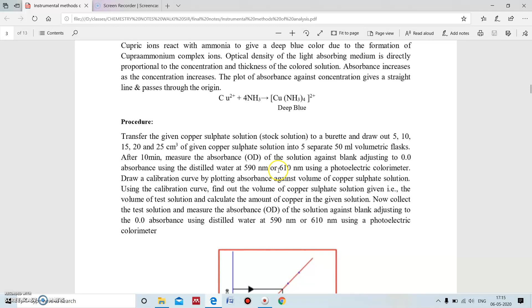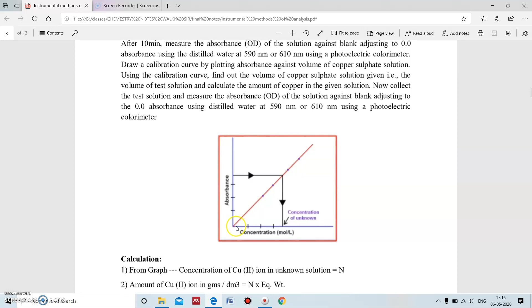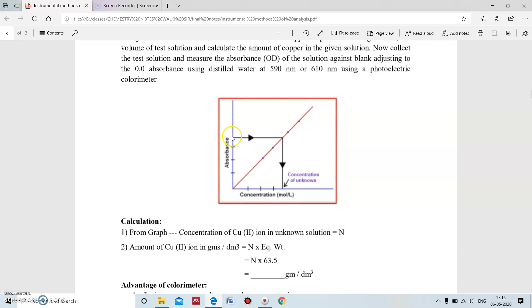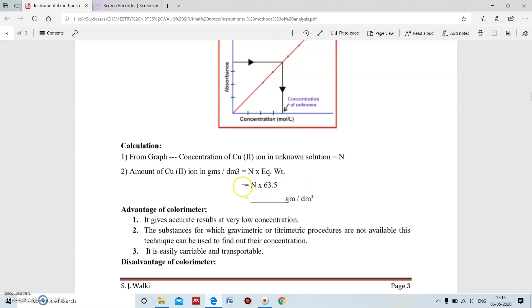In order to standardize the instrument, we use distilled water for adjusting zero, because distilled water is completely free from impurities. Then, using light of wavelength 590 to 610 nanometers, we measure the absorbance. After obtaining the readings for all standard solutions, we take our test solution and record the optical density. Then we draw the graph of absorbance versus concentration, and we get a straight line passing through the origin. Noting the absorbance of the unknown solution, we calculate its concentration using the following equations.